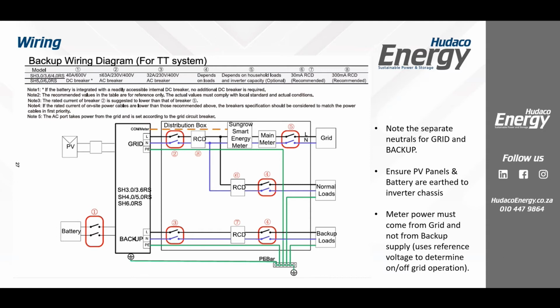Then you've got your normal loads. So these are your non-essential loads. Here you would normally have geysers, stove. You know, this would be what would be existing in the client's DB over here. And then, of course, we feed into the inverter. Now here they show a breaker and an RCD. I have seen some clients install without this RCD here. And I have seen this feed breaker not only be a feed breaker, but also a bypass. So if you've got a bypass, it'll happen here and it'll just bypass down to here.